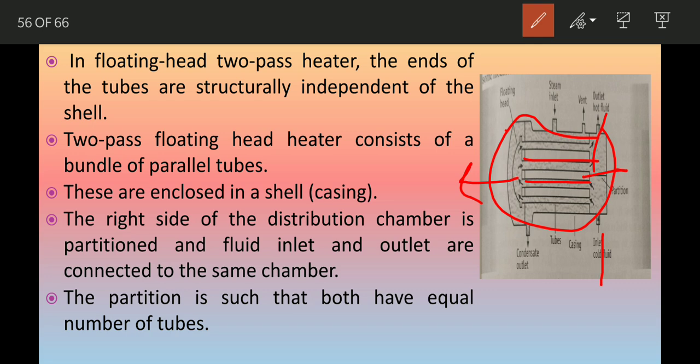The other end of the tube is embedded into the floating head. Steam or vapor is introduced through the inlet provided to the shell. Provisions are made for the escape of non-condensable vapor and exit of the condensate vapor. Here is the steam inlet; here you can collect the condensate vapor, and if there is gas, that will be passed from here. This is the construction.